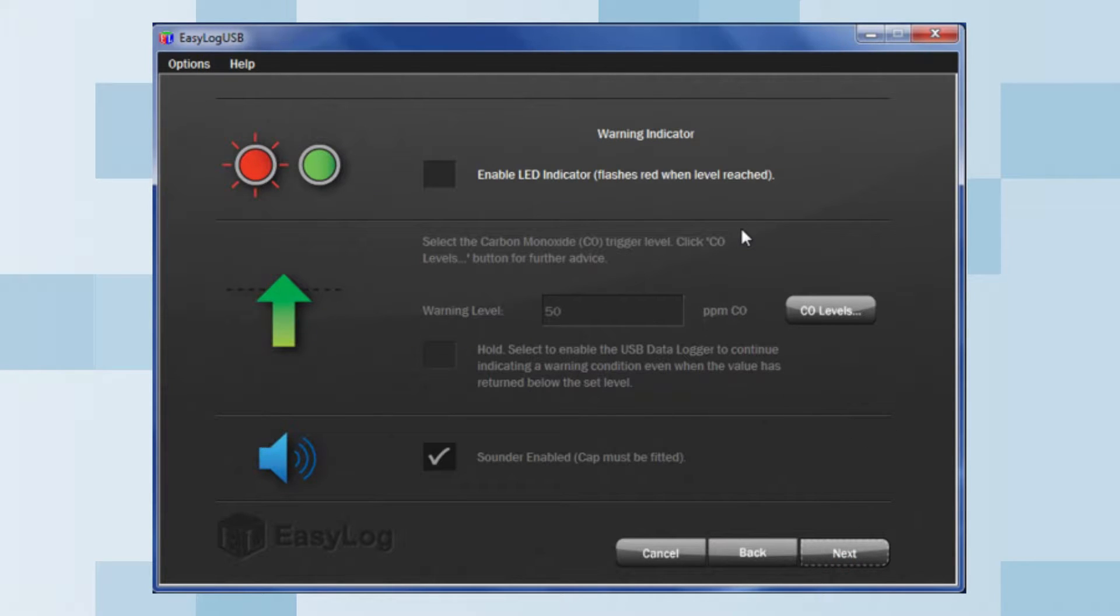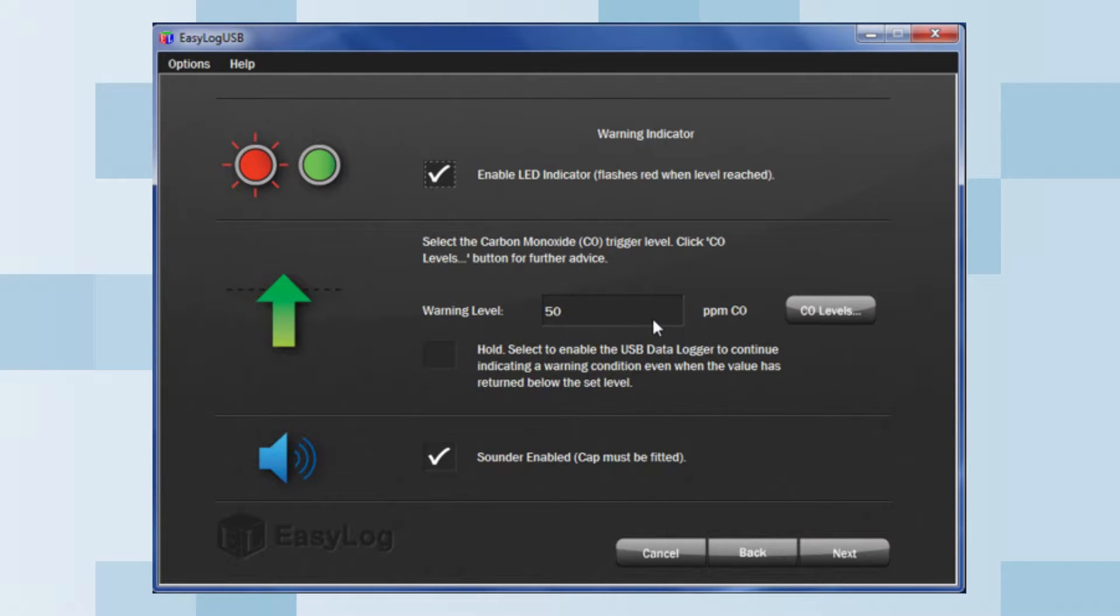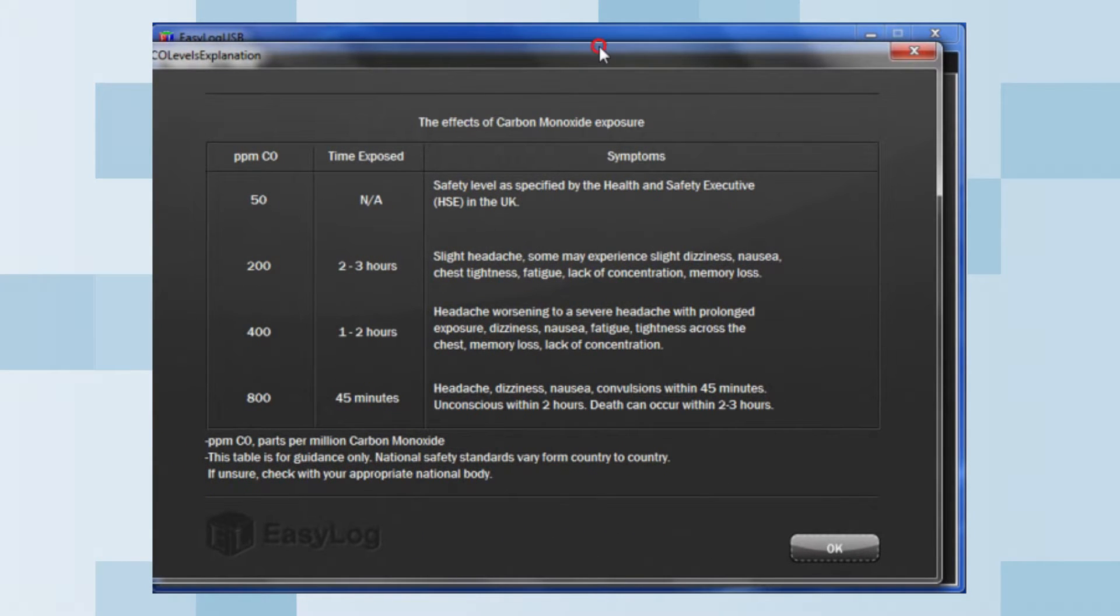This next page is the warning indicator. If you tick the checkbox here, you are presented with a few options. Select the carbon monoxide CO trigger level. When you click the CO levels button, it brings you to a table with guidance on the effects of carbon monoxide exposure.